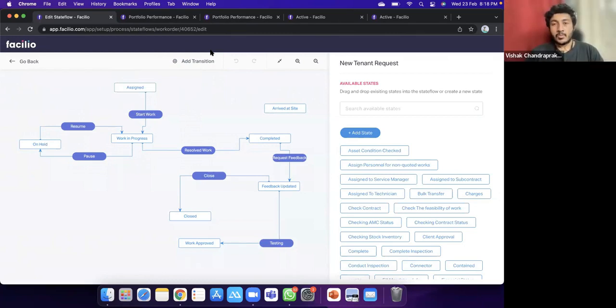I'll take it one step at a time. The root cause analysis is really driven by Facilio's data model, which is completely configurable, and we build a process specific to that property. This associates assets to the locations they're serving, and we keep track of the underlying parent-child relationships between different assets. So we know a VAV is serving a space, that VAV is served by a main AHU, which is connected to primary and secondary pumps, which are connected to the chiller boiler. We're able to digitize that entire system, getting data points from all these different parts and understanding how they relate.